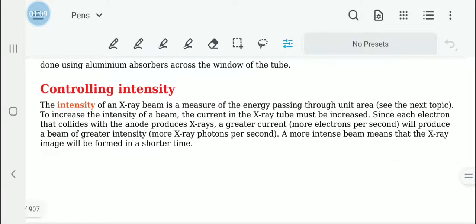We can control the intensity of the x-rays using electricity. If we increase the current in the x-ray tube, more electrons will be released and as a result, these electrons will produce a beam of greater intensity. The intensity of an x-ray beam is the measure of energy passing through a unit area. More electrons passing per second will produce a greater intensity, and as a result, more x-ray photons are released.